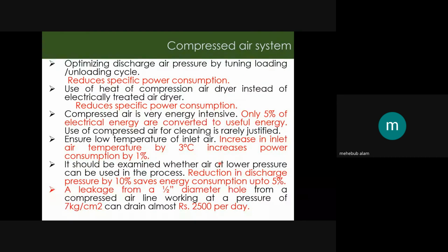In the case of compressed air systems, compressed air is very costly, and it is required in any power industry for two purposes: to operate the pneumatic valves or actuators, and for cleaning. For cleaning purposes, a service air compressor is required, and to operate the pneumatic valves, an instrument air compressor is required. So specific power consumption is to be carefully examined. As we said, compressed air is very costly because only 5% of electrical energy is converted to useful energy through compressed air.